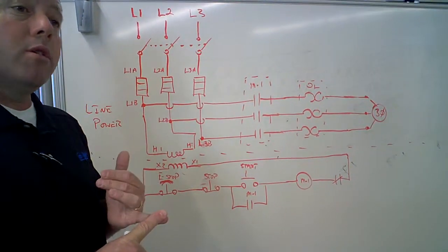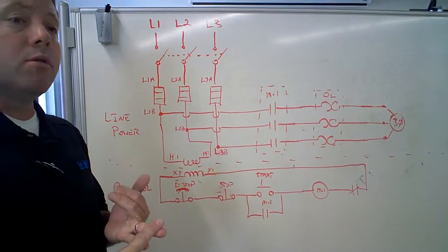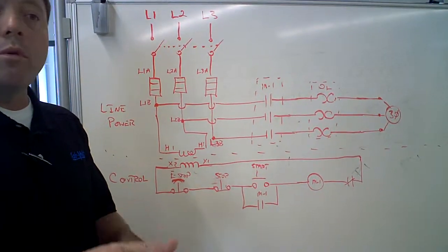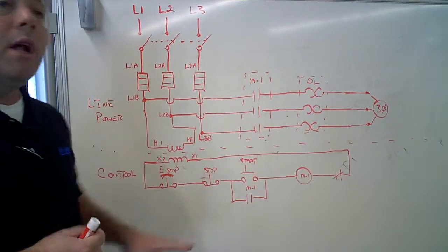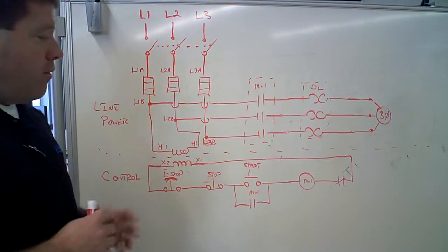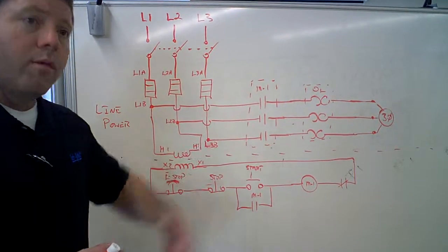The control circuit could be any voltage. You can see it as 480-volt control circuits. You can see 277, 240, 120, 24-volt. I mean, there's a wide variety of voltage there. The voltage of the control circuit does not matter. It still provides the same thing. I can still turn on that 480-volt motor with a 24-volt controller.